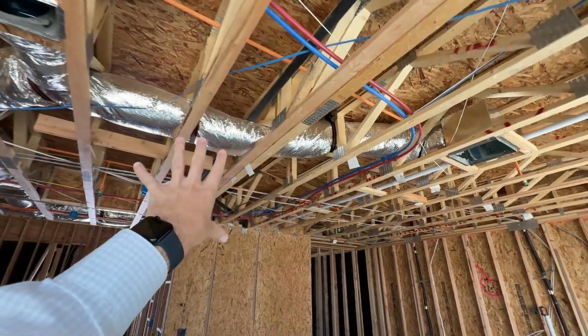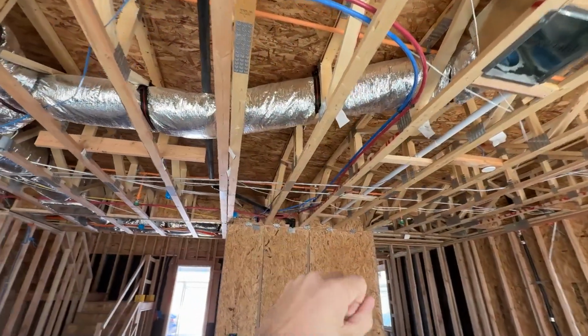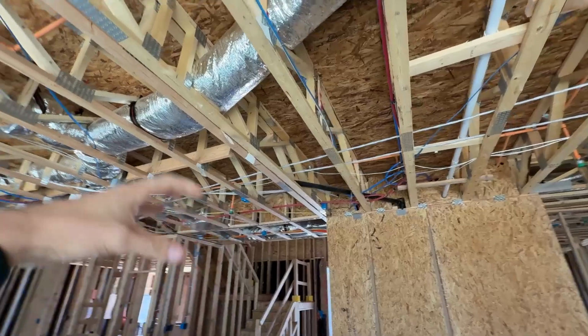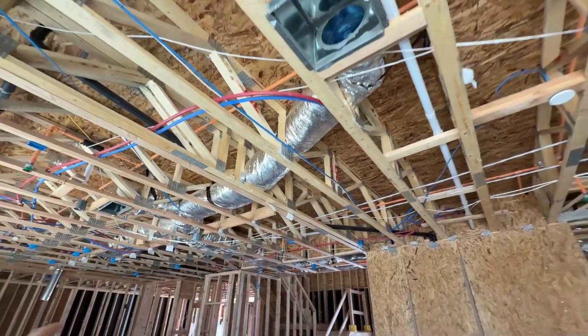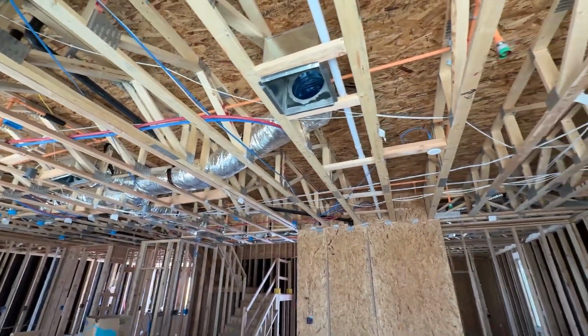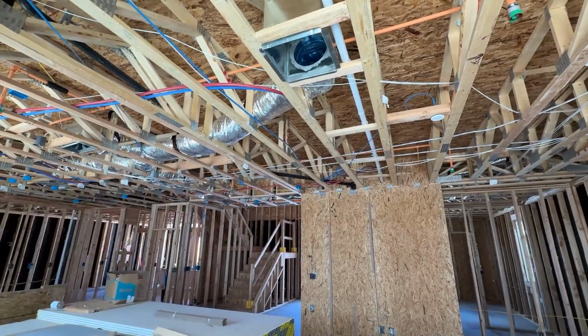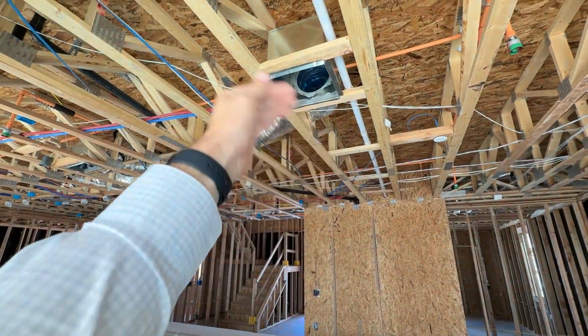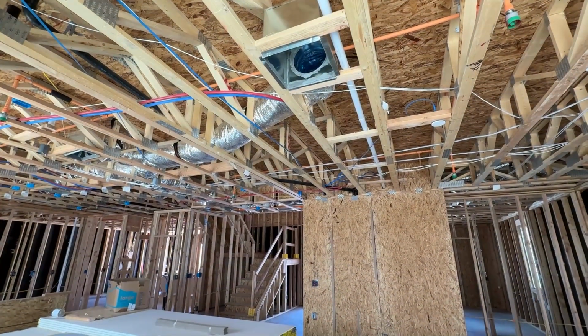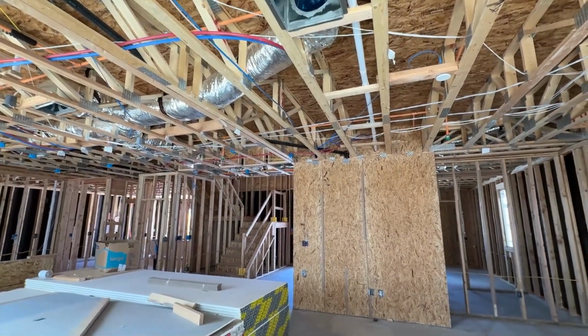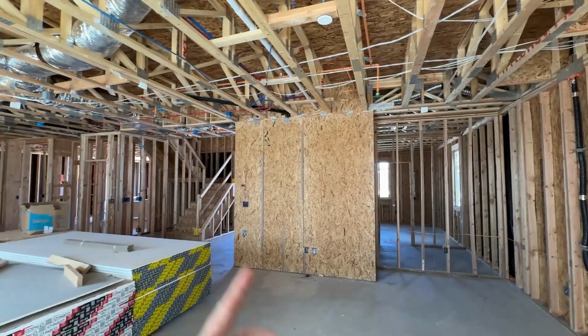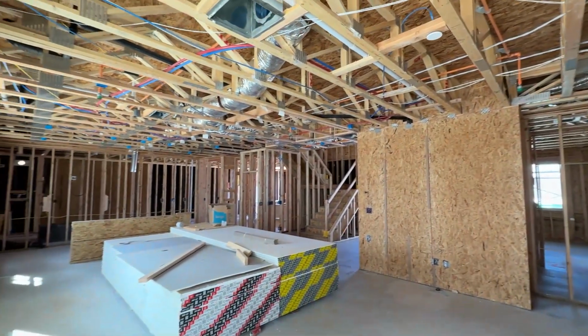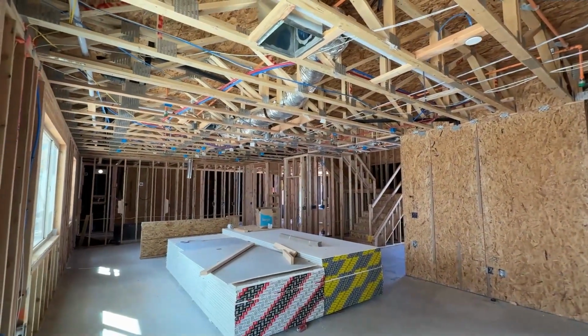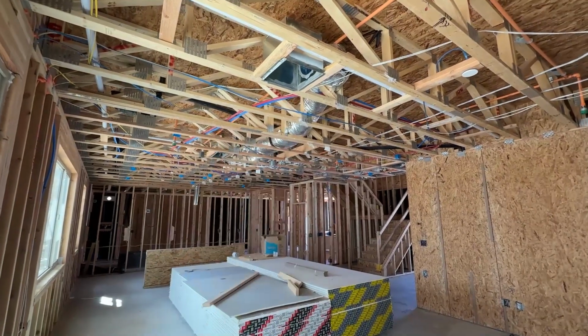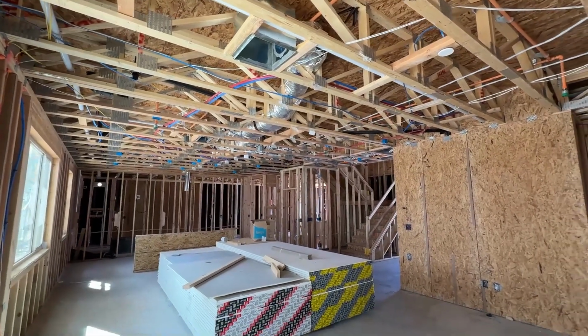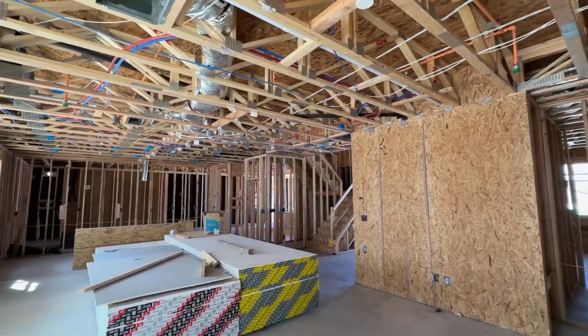What you have to watch out for is when something is really restricting the airflow. If you don't pay attention to that and you build the house, then walk in and there's not enough air coming out of one of the vents, you probably will never notice. Even if the inspector checks the temperature and it's coming out pretty cold, if you don't have enough flow into the vent coming out from the register, you might have an issue.